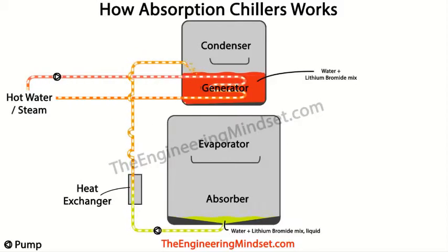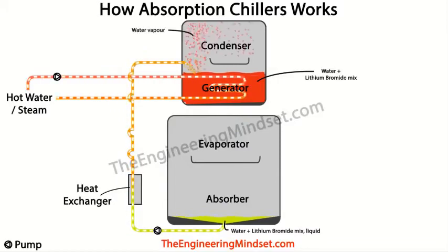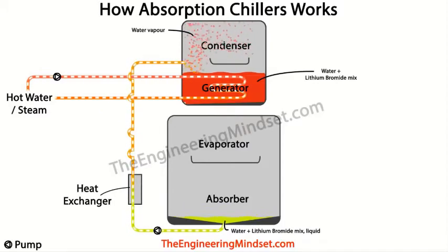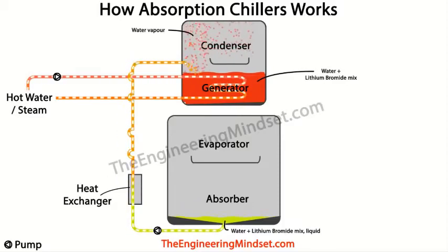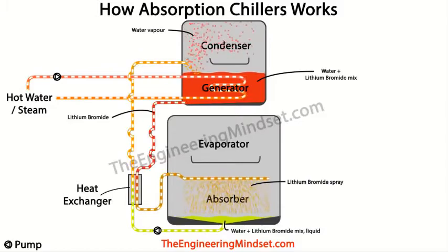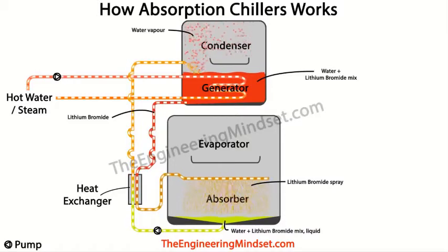Next, heat is added to the reservoir containing the lithium bromide and water, and this will begin the separation process that we saw earlier. Now this heat is usually in the form of waste heat and will typically come from hot water or steam that's being pushed around a heat exchanger of tubes inside the generator. The heat from this hot water or steam causes the lithium bromide and water to separate. All the water particles will start to boil off and will fill the condenser with a hot water vapor or steam. Then the heavy lithium bromide particles will sink to the bottom and form a concentrated liquid.